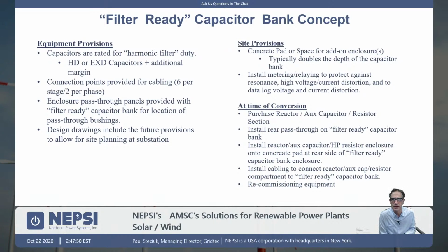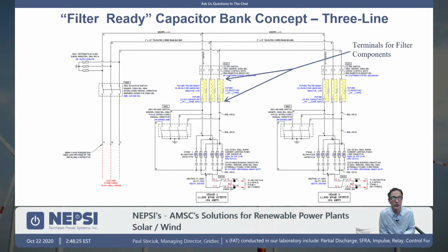The other thing that we would recommend is that you install a Schweitzer 735 on the capacitor bank, and also on the mains to the plant itself. So you've got the main incomer, put a 735 there, a power quality meter from Schweitzer, and then also put one on a cap bank. If after startup you have problems, you do not need to send somebody out to site to take harmonic measurements. You can pull the device itself and obtain the necessary harmonic data for us to do a filter design. So we recommend that because, again, the cost savings are significant if you do have a problem.